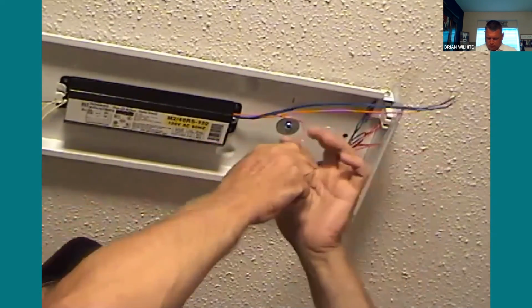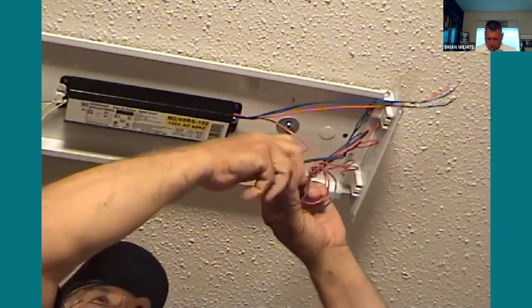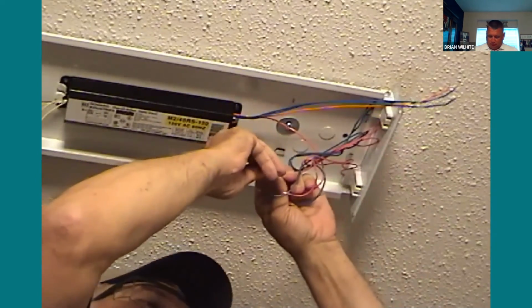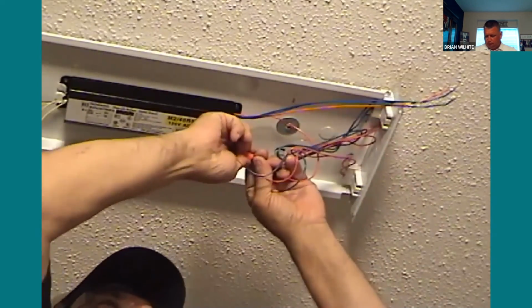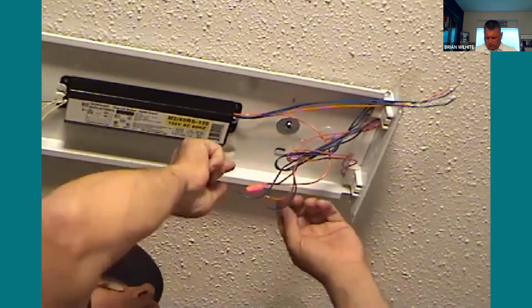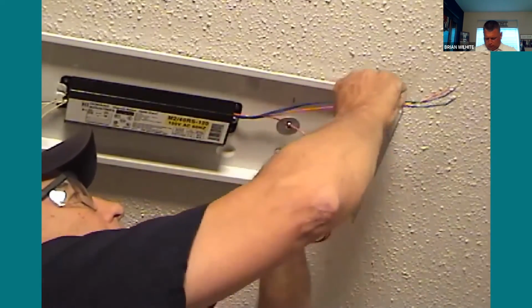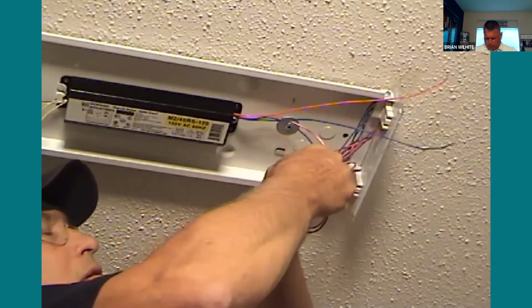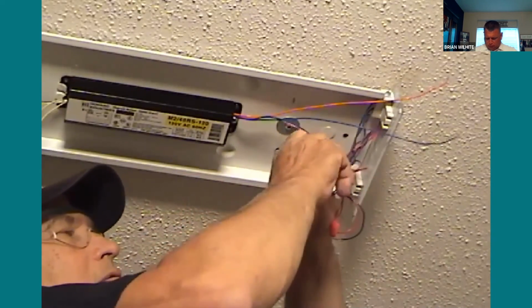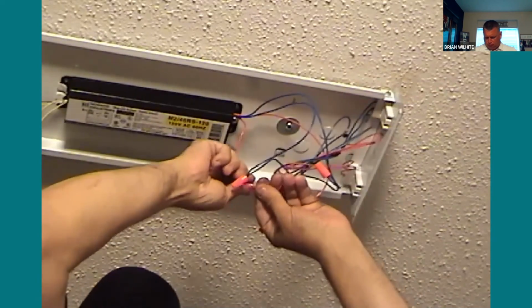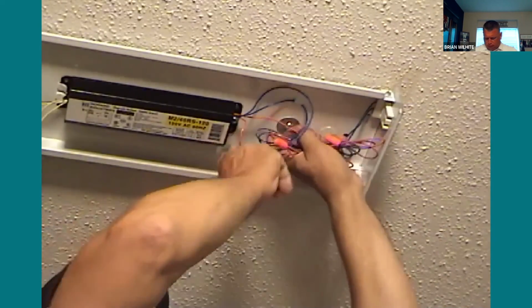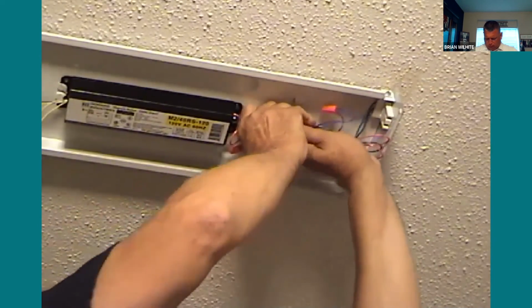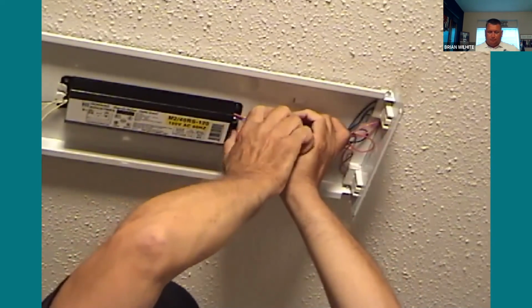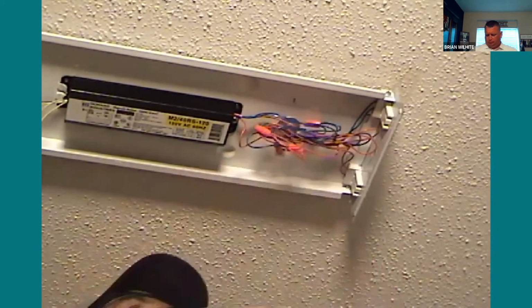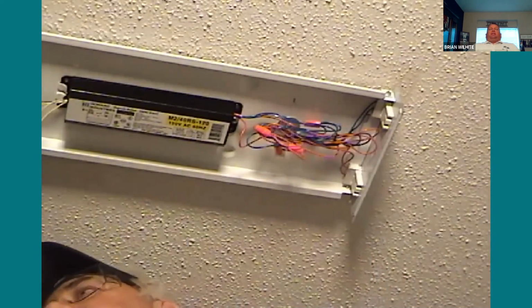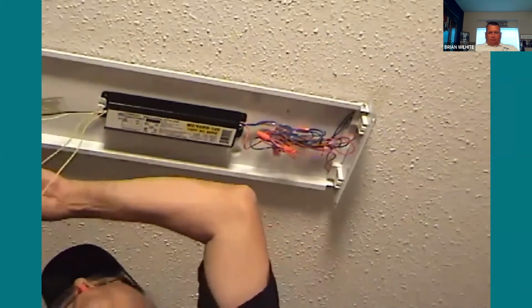The wires are stripped. Now he will reattach wires matching colors. Wires will be screwed together and secured using wire nuts. As the wires are connected, they're bunched together properly to allow clearance of the ballast cover to be reinstalled.